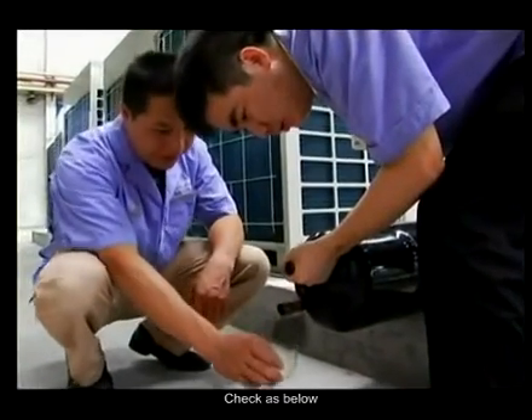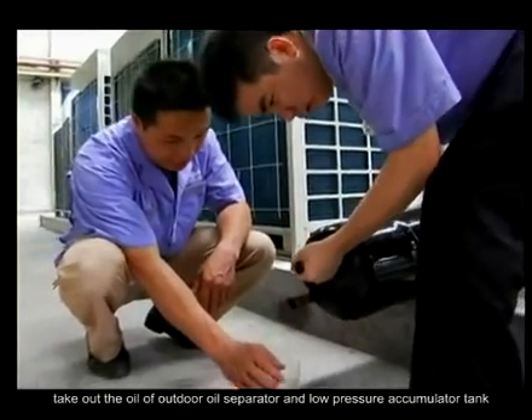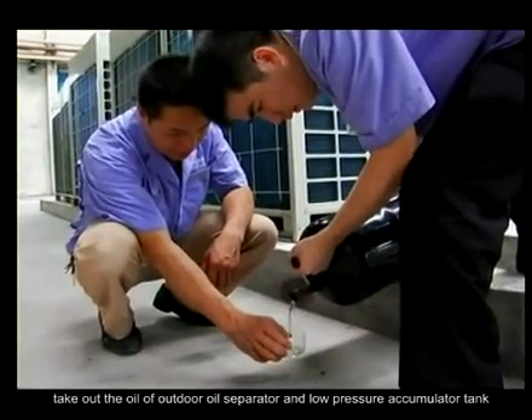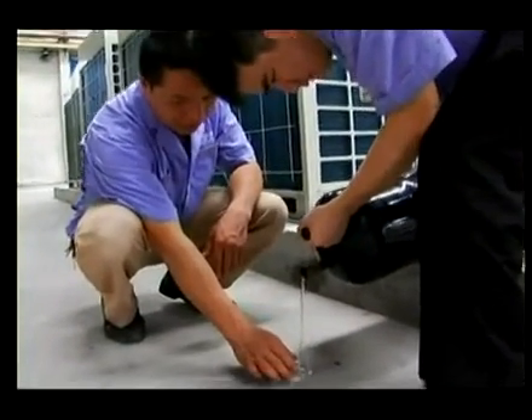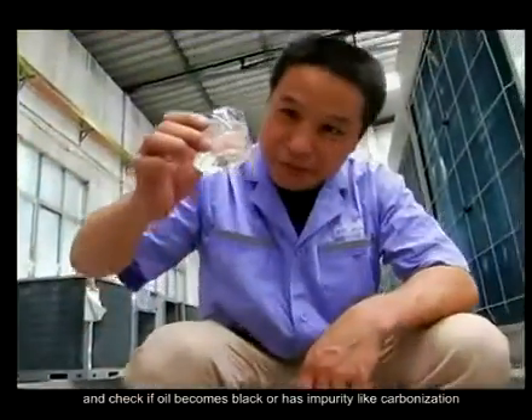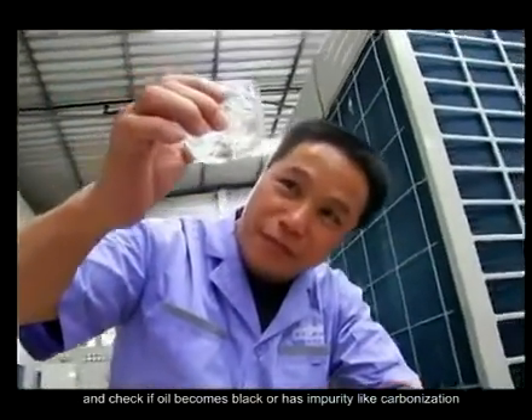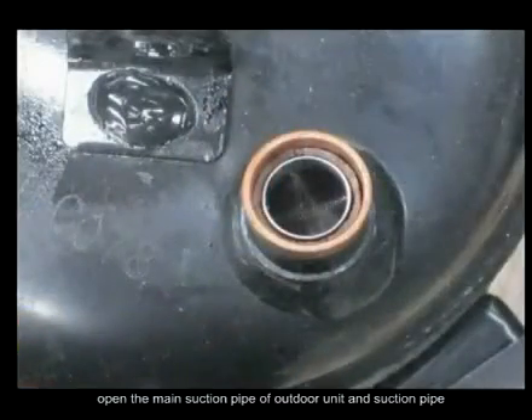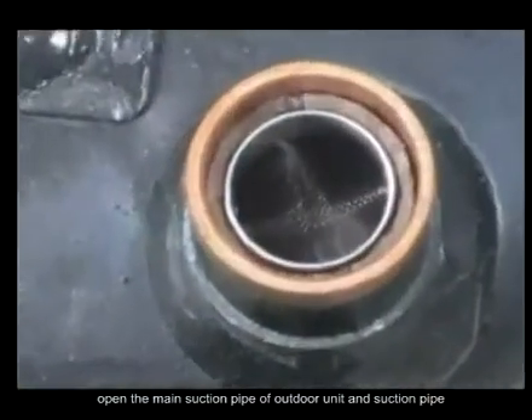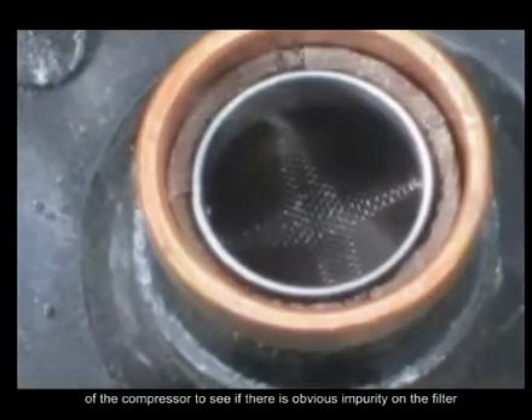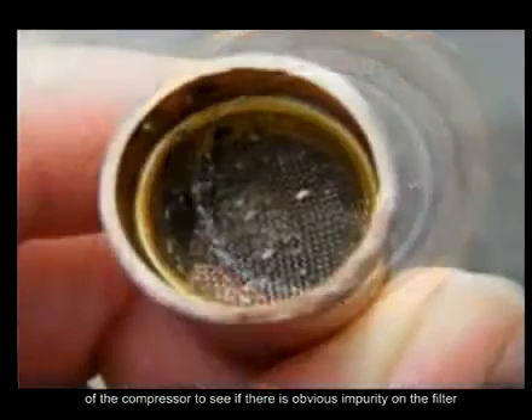Check as below. Take out the oil of the outdoor oil separator and the low pressure accumulator tank and check if the oil has become black or has impurity like carbonization. Open the main suction pipe of the outdoor unit and the suction pipe of the compressor to see if there is obvious impurity on the filter.